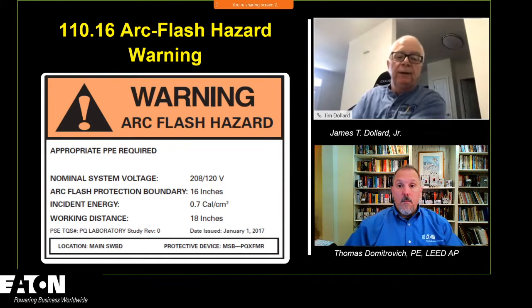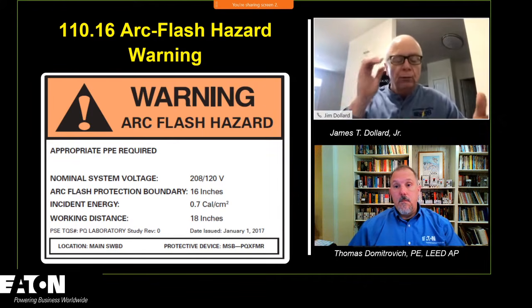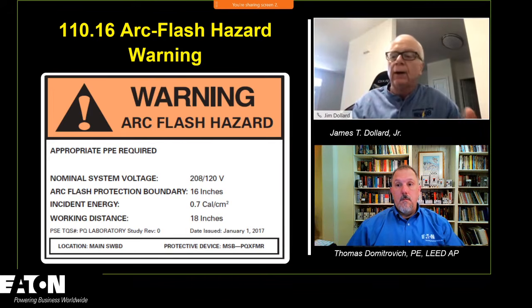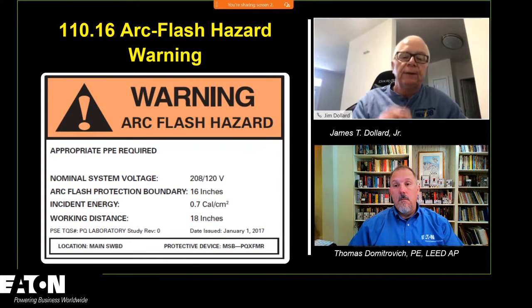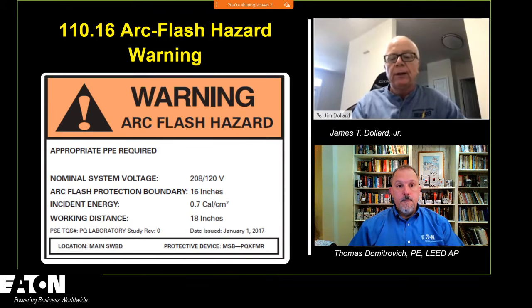It's all about where the rubber meets the road—where that individual goes in to energized equipment, with justified energized work. This type of label, from an incident energy analysis, is what that individual needs, because now they'll know the arc flash boundary and what they need to wear with respect to arc-rated clothing.